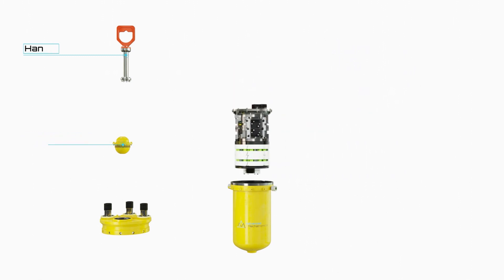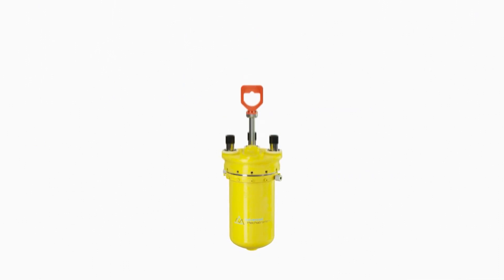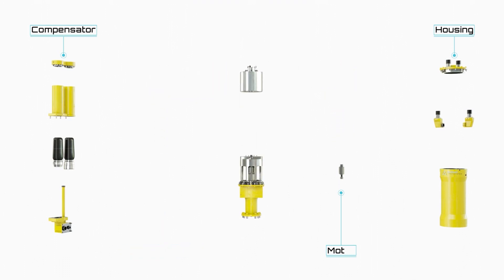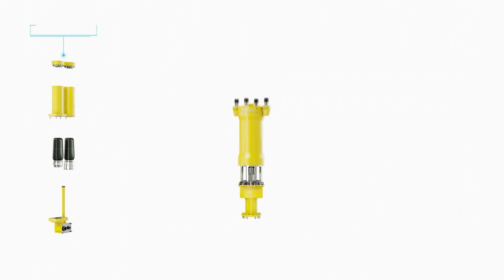The nitrogen-filled one atmosphere housing ensures continuous operation for more than 25 years. The actuator includes a dual channel brushless motor that through a linear mechanism delivers maximum torque to accurately position the valve to prevent and recover a potential surge of the compressor.